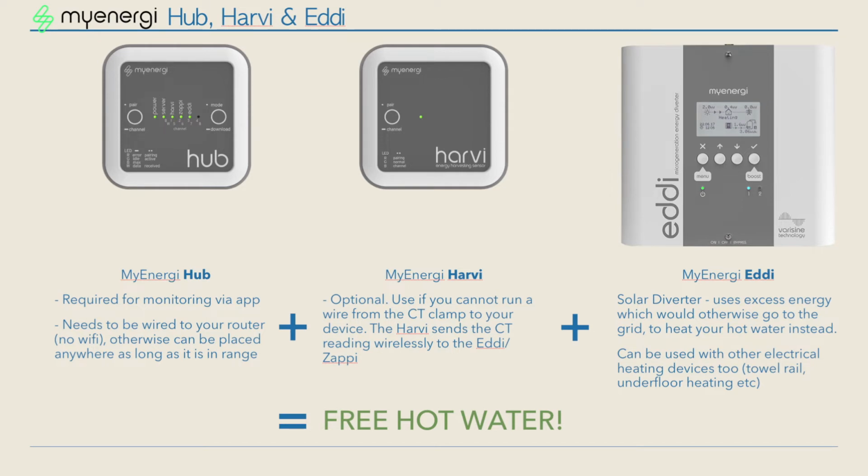The Eddi has also got two outputs. So what I mean by that is it can control two devices. So in my case, I actually have two water tanks in the house, and therefore I've got two immersion heaters. So I've connected one of the outputs to the first tank and the second output to the immersion heater in the second tank. So I can actually heat both separate tanks of water via the system. The Eddi can only heat or power one device at a time, but in the settings you can tell it what priority you want it to give and how frequently it should check back with the other device just to keep them both under control.